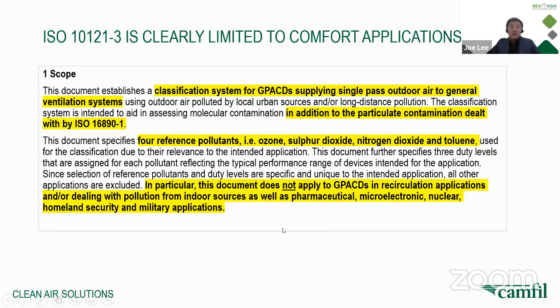It's good to have all the standard, but we also want to be clear on what this standard applies to very strictly. Take note, this ISO 10121-3 is clearly limited to comfort applications only. So it's actually referring to GPACDs supplying single pass outdoor air to general ventilation systems. Okay, and it's actually a supplement in addition to the particulate contamination dealt with by ISO 16890, which is your particle filters. So actually it's an add-on to the particle filters that you have. So again, the 4 contaminants, the pollutants that we target, are ozone, sulfur dioxide, nitrogen dioxide, and toluene.